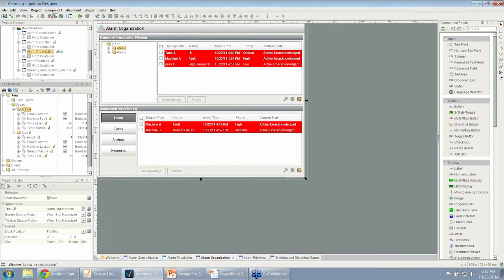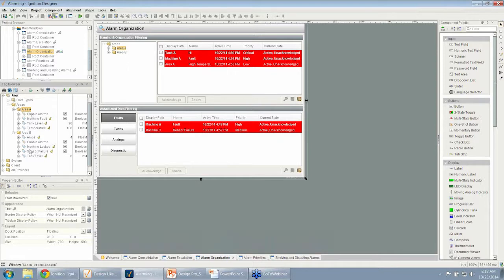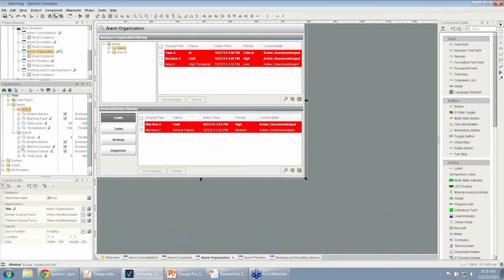That first method is to use the folders for filtering. By just putting all three of these alarms in Area A and the other four alarms in Area B, now I can go on a screen and see all the alarms that are currently active in Area A, all the alarms in Area B, as well as history and for notification. I may notify a different list for Area A versus Area B. So if you organize your tags and think of a hierarchy in this way, you can use that to your advantage in the alarming system.